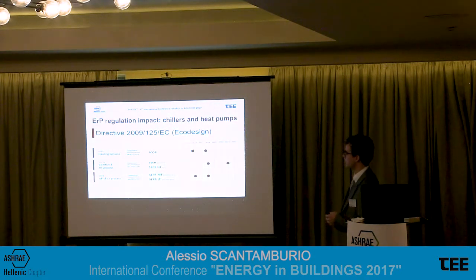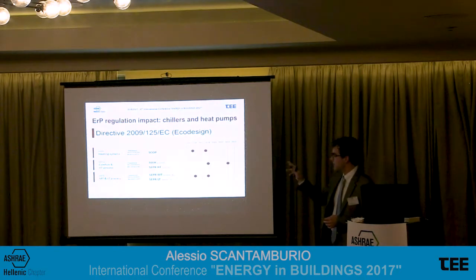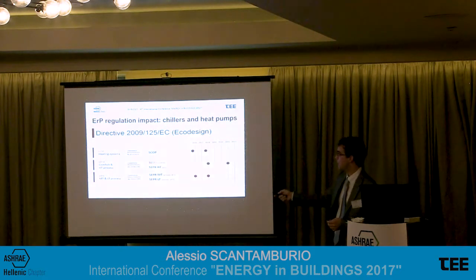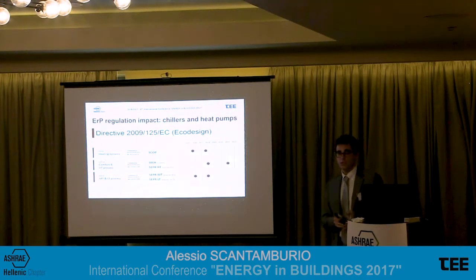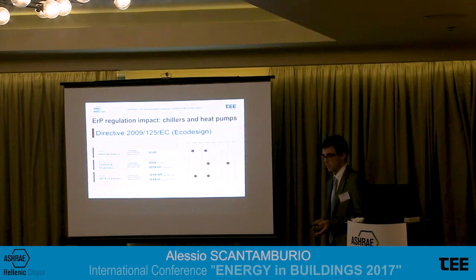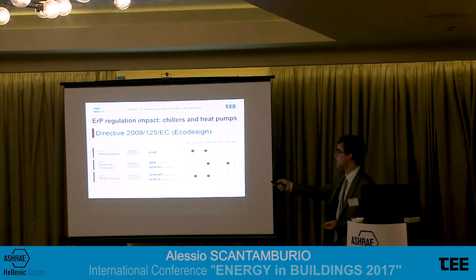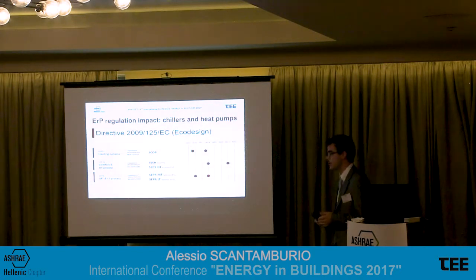So inside the directive regarding chillers and heat pumps, we have 3 regulations. The first one, the 813, uses the SCOP and is regarding heating systems, so systems that produce hot water, basically. And we have 2 tiers. The last tier entered into force last September, setting minimum efficiency levels.